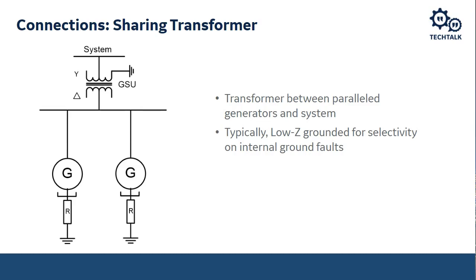When we talk about bus-connected generators sharing the same GSU, it's the same scenario we talked about. This would typically be low impedance grounded for selectivity during internal ground faults, because we want to make sure that we detect that ground fault, and we know where that ground fault is, so that we take the right generator out of service and prevent a fault on one piece of equipment, like the generator on the left, from causing damage to the generator on the right, so causing collateral damage.